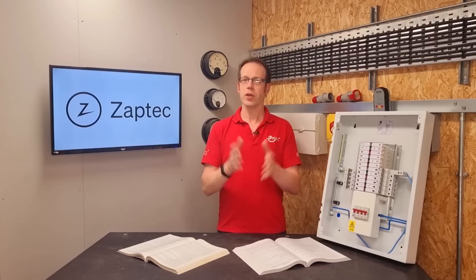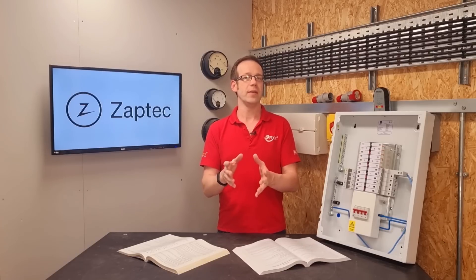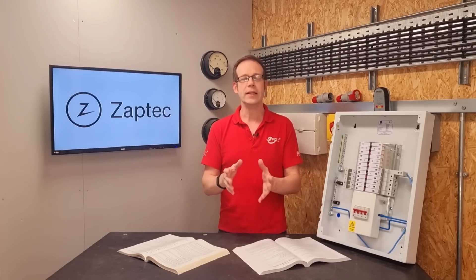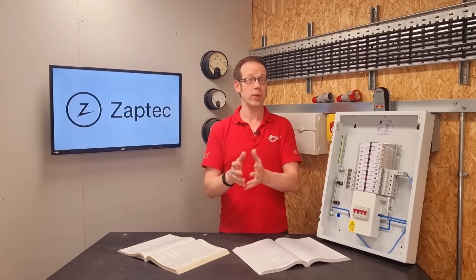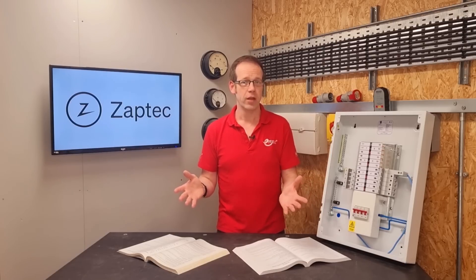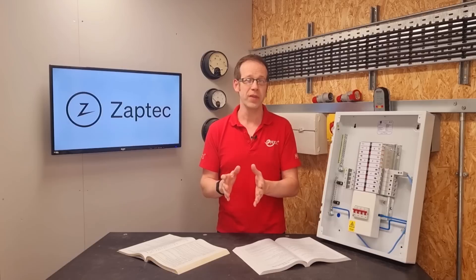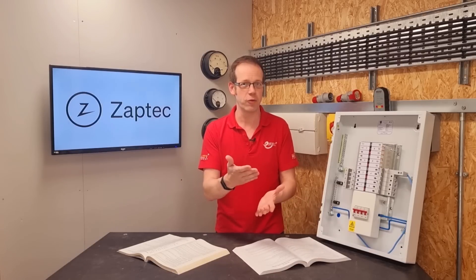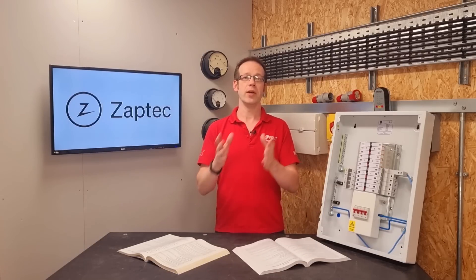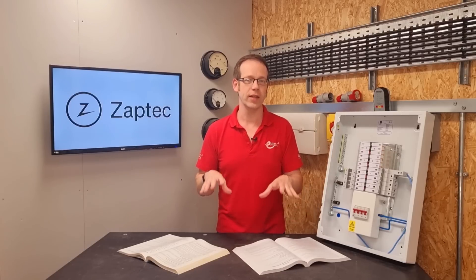In a three-phase system though, the current in the neutral works a little differently. In fact, if the loads on each phase are perfectly balanced or equal, then the current in the neutral would be zero and you can actually do without the neutral connection entirely. So if a PEN fault occurred on a perfectly balanced three-phase system, then there'd be no neutral current trying to find its way back to the transformer and the voltage between the bodywork of the car and the actual earth we walk around on will be effectively zero.